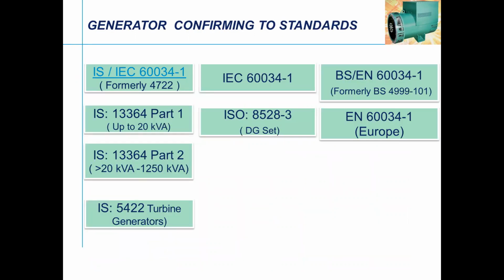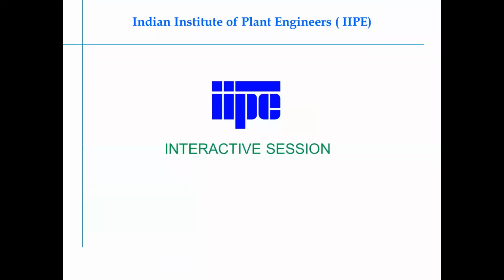Coming to our generator standards, this goes with the IEC standards. Anything we do has to be with a standard. Of course, in part 1, IS 4722 was there, which has been withdrawn by our standards team, and it is now 60034, which is part of it. Again, for ratings, there is a different one up to 20 kVA. Some ratings are given in part 1, and part 2 covers up to 1250 kVA. For turbine applications, there is a different one. So these are the different international standards. The generator standards have been built in.